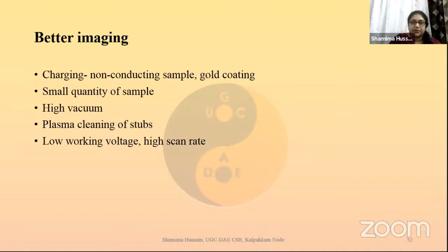And these are the other things which might affect the imaging. Sample preparation is very important. We should have a very high vacuum level. Gold coating, as I said, we need to have the sample surface conducting. That doesn't mean we just coat it with too much gold. Too much gold will just suppress all your features. So we need to have a very adequate amount only, which is usually done by sputtering onto the sample, and it will be about 2 to 3 seconds, a maximum of 4 seconds. That's good enough. It depends on what voltage you're using.